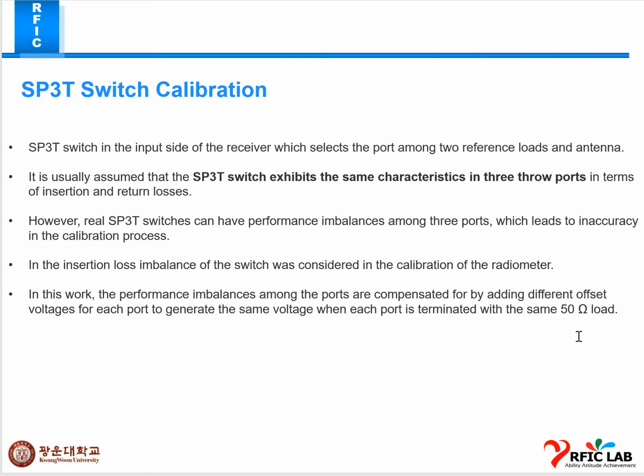However, in reality the SP3T switch can have performance imbalance among the three ports. This may lead to inaccuracy in the calibration process, and the loss imbalance of the switch can be considered in this calibration of the radiometer. The performance imbalance among the ports is compensated by adding different offset voltages for each port to generate the same voltage when each port is terminated with the same 50 ohm load. That was the SP3T switch calibration.